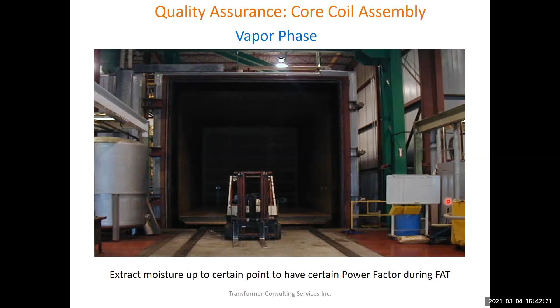They can use very pure refined oil, which has better dielectric properties, not the same oil used in the transformer at the site. They can control the environment of the factory testing bay so that even if the manufacturer is aggressive in design, and there's contamination like dust or moisture inside the transformer, it won't fail, because the manufacturer is testing with very pure refined oil in a controlled environment. The test bay environment is not the same as the environment in the field.